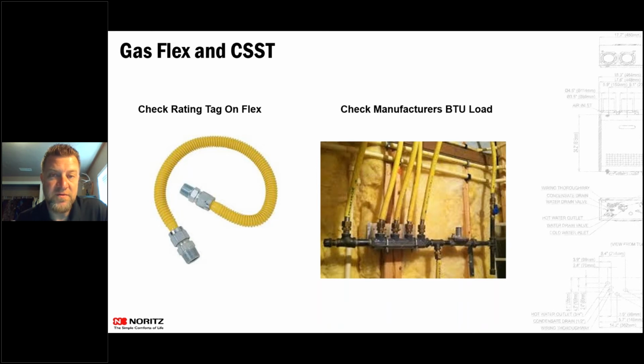There are a lot of new regs out there too, what they call zero clearance regs, where they have manufactured that into those regulators. Like we had a huge job in Colorado a couple years ago where they had regulators that they could put directly on the units because they didn't bleed through or pressure or anything like that. So there are some of those out there, but rule of thumb, try to keep it at least 3 feet away from there. And also check the manufacturer's BTU load on their CSST because it's different than it is for iron pipe. Each manufacturer of CSST has different BTU loads that they can run through their pipes. So make sure that you are checking that BTU load on that CSST to make sure that it is exactly what you need for that system.